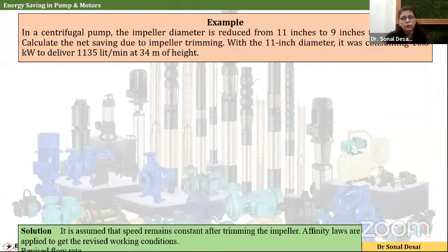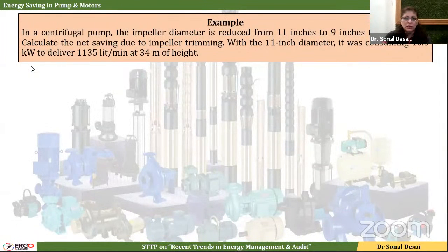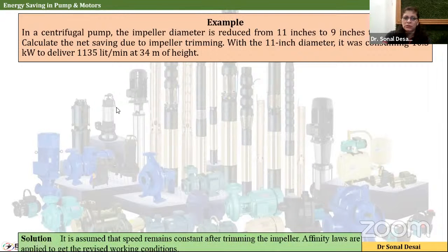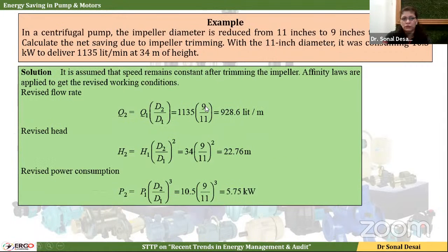Next, we are going to understand the effect of impeller diameter. In this case, a centrifugal pump is given, wherein the initial impeller diameter is 11 inch, which is reduced to 9 inch. By this time, I believe you understand that the impeller is the center portion that imparts velocity to the fluid, and it is the main part of the pump. So the initial diameter is 11 inch, which is changed to 9 inch, and we have to look at its effect on the power consumption as well as the head delivered and flow.